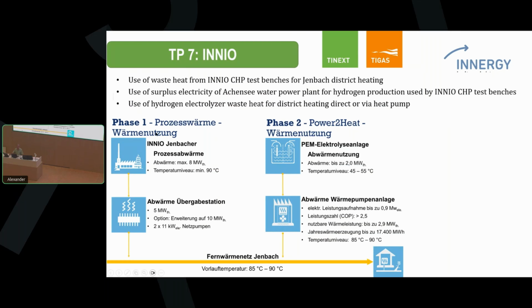So that's what you can see here in phase one. This is INNIO, the waste heat from testing the CHP systems, something around 8 megawatts at 90 degrees. A 5 megawatt station is already installed. In the second phase, what is already installed is the electrolyzer to produce the hydrogen, and as I said, around 45–55 degree waste heat could be used. This is not installed yet, but hopefully coming in future. And last but not least, using a heat pump system to use heat from the small river passing by is also planned.